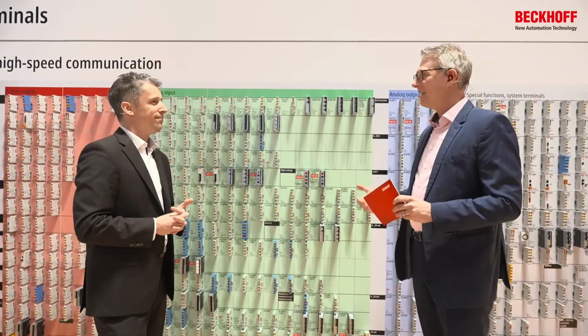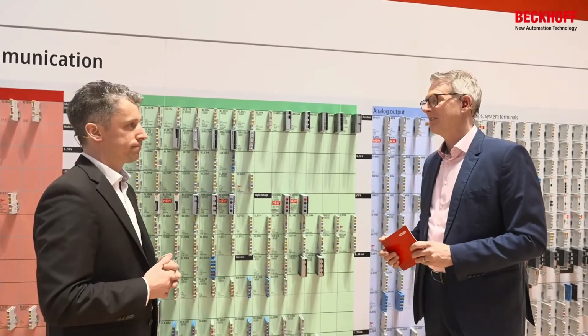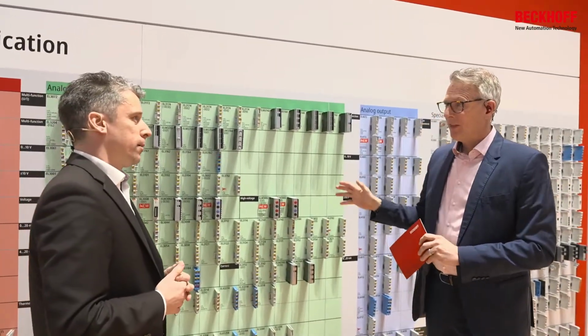So EtherCAT synchronizes all the devices, and then we can be sure that the measurements, even though they are separated, were taken at the same time. Then we can multiply the digital U information, voltage, with the physically measured current and get our voltage, power, energy, and harmonics, even though the single terminal doesn't have any voltage information. So speed matters, so EtherCAT performance is also helpful for this, because with the distributed clock system, it's easy to do this. Now, this is one thing, the voltage.